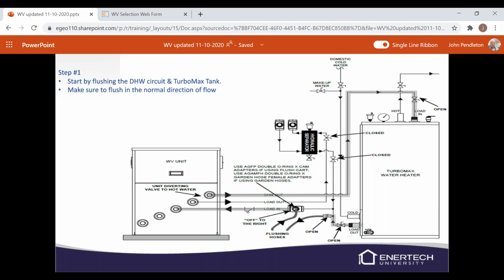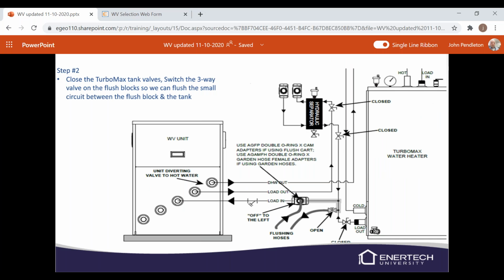On step 1, we would prefer you to flush the domestic hot water circuit first, and you can flush through the unit and through the tank in the normal direction of flow. Make sure you've got your valves open for the tank and that they're closed off. If you've got a hydraulic separator or a buffer tank, close off that circuit, and we're just going to flush through the load in, and then through the domestic out, through the tank, and then back to the flush cart.